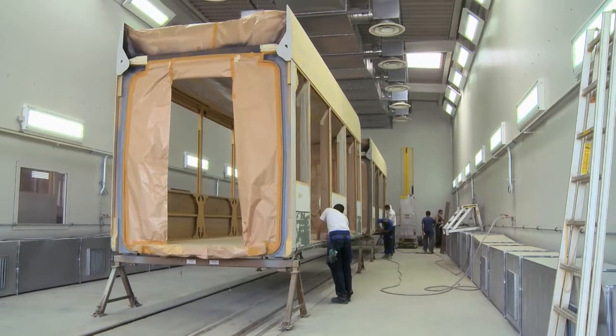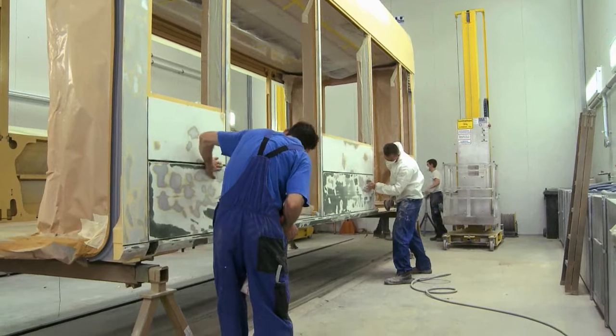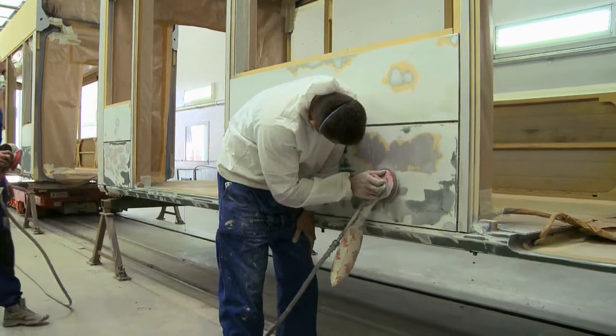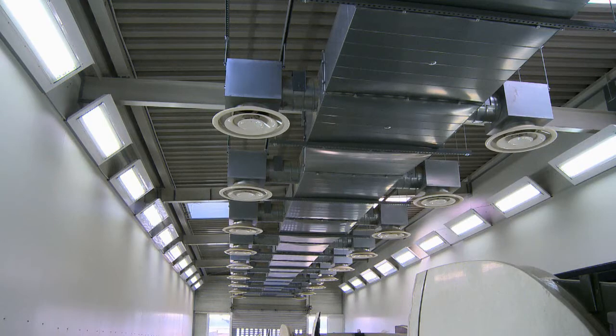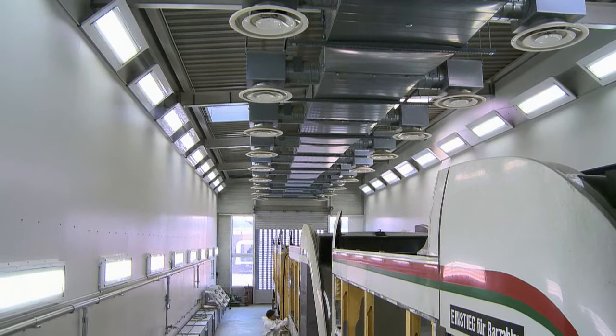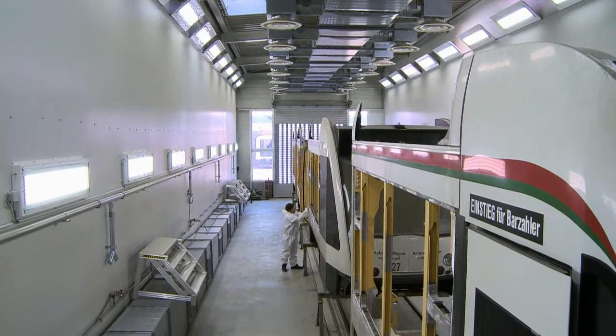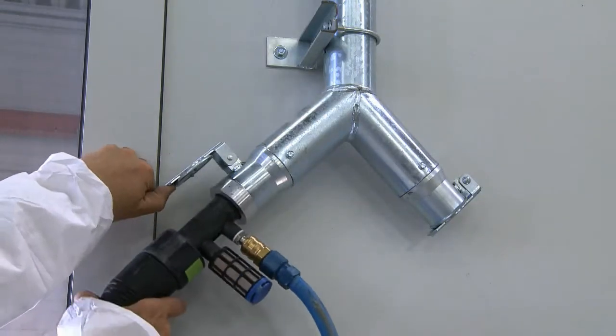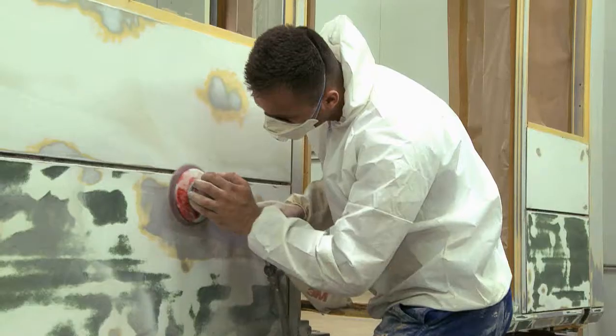Today, the early shift ends with sanding work performed on the empty carriages. Fresh air can be targeted at the various work areas by means of interconnected sections. With a system in place to renew the air 18 times an hour, all of the dust created by the work process is removed, whereby the majority of sanding particles are already extracted right at the machine.